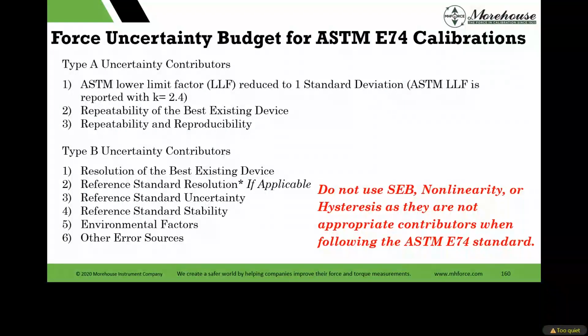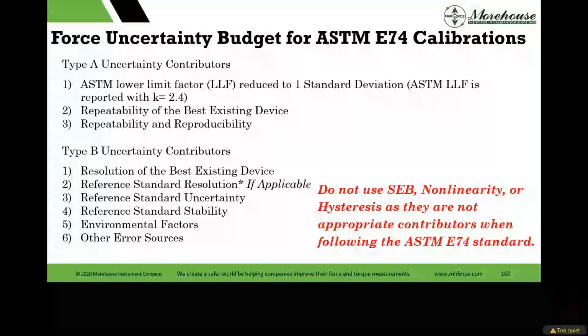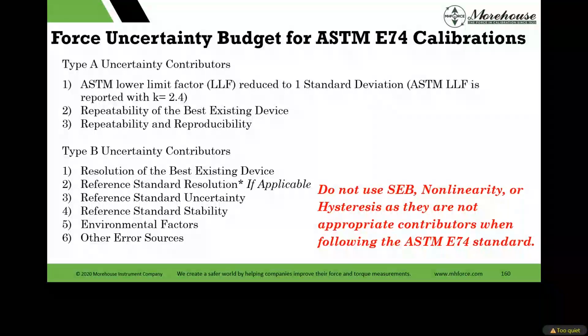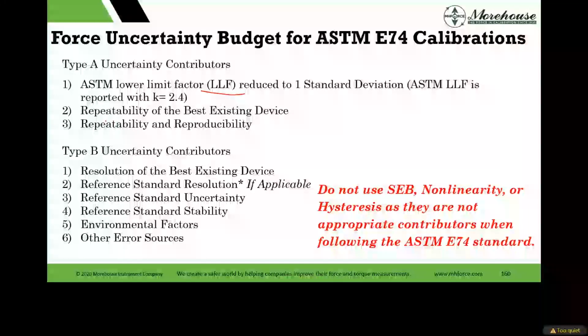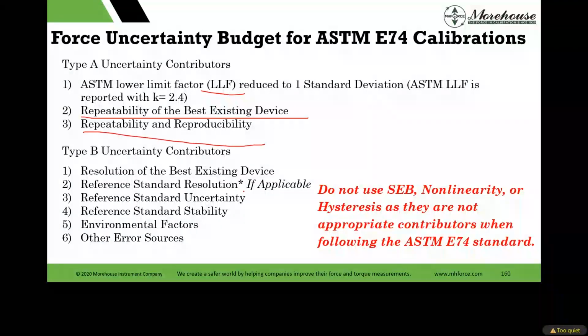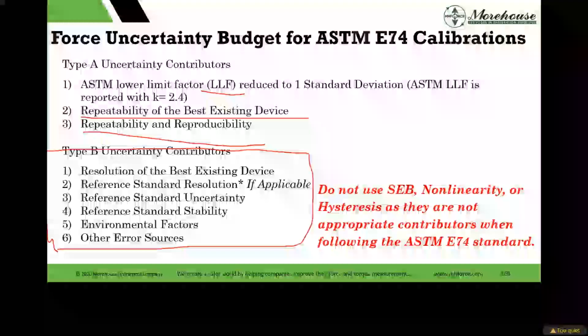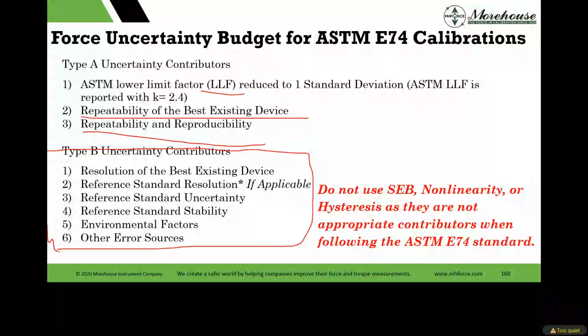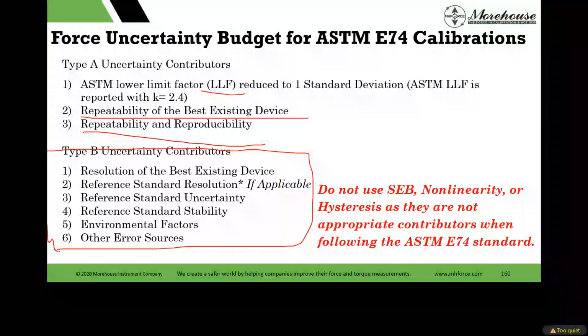I have a quantified expected performance of my device in that ASTM lower limit factor, which is a Type A uncertainty component. Type A is statistical analysis. Type B is basically other methods. Super bland and super simplified for this discussion. And then I start doing an uncertainty analysis. Our guidance is real easy: take that lower limit factor, do some repeatability studies, do your R&R between technicians, and then I'm going to start doing all this other stuff. The 5 R's in the E74: resolution of the best existing device, reference standard resolution, reference standard uncertainty, reference standard stability, environmental factors, all of this stuff.